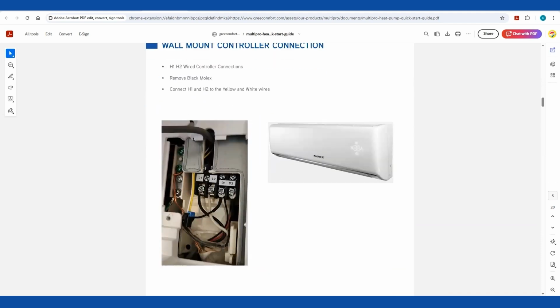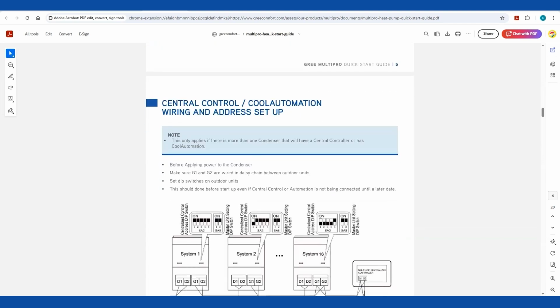All right, so moving on here, some more things on the quick start guide. Just in case you are doing a wall mount and you need to hook up a wire controller, these yellow and white wires right here actually go up on the board to H1 and H2. These controllers are hardwired with just 18-2 stranded wire, just like your comms wire. So you're not going to have a Molex plug. So just cut that off and you wire nut to yellow and white, and it is not polarity sensitive.